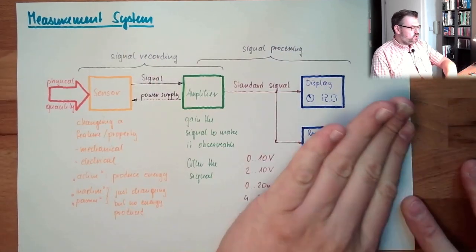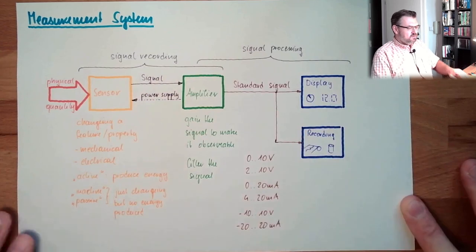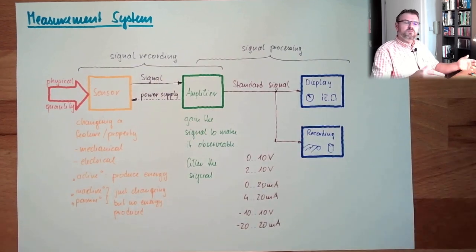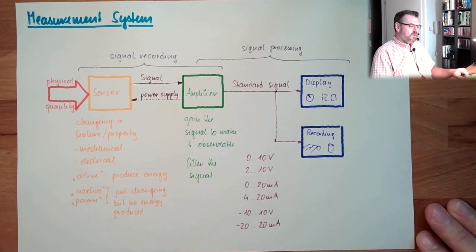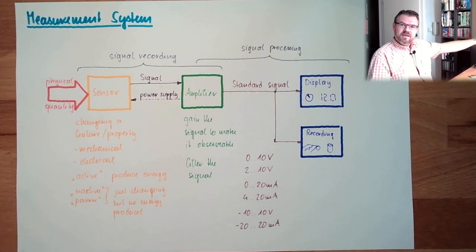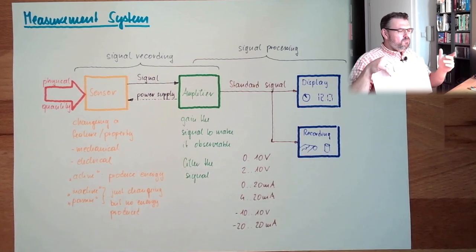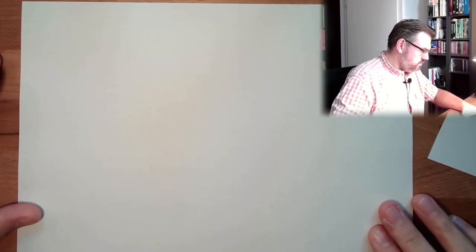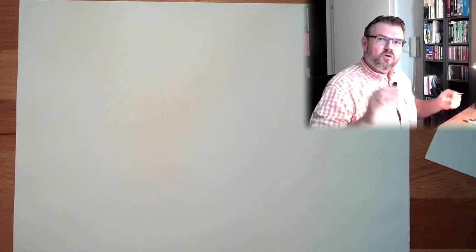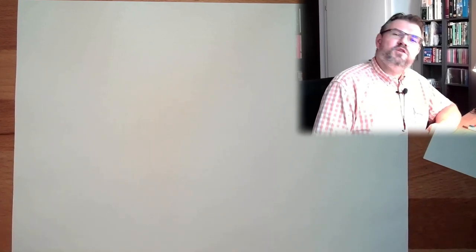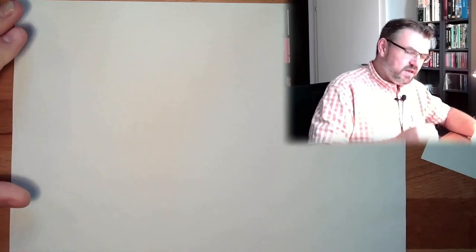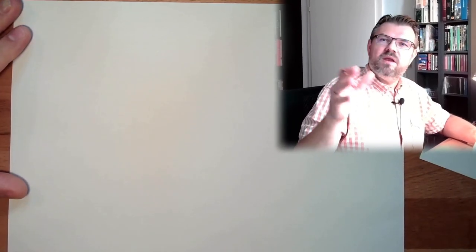So these standard signals are very usual, and also the processing and displaying items are usually adapted to the standard signals. For instance, if you're recording with the help of a PLC — a programmable logic controller — then there are analog input cards which can read 4 to 20 milliamps, or 0 to 20, or 0 to 10 volts. You can buy them off the shelf, and this makes things easier to use standards. So this is the basic structure of a measurement system.